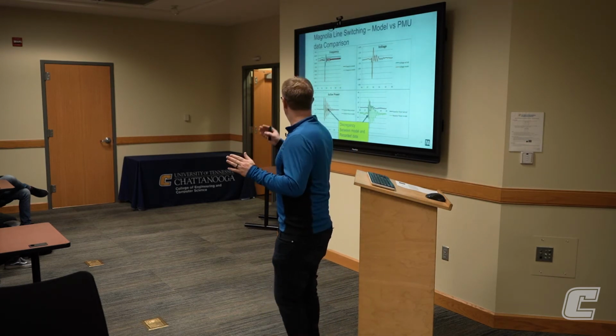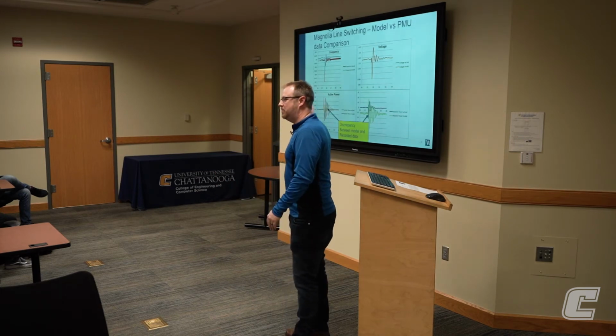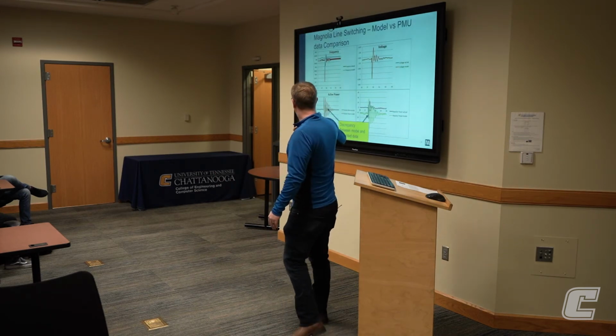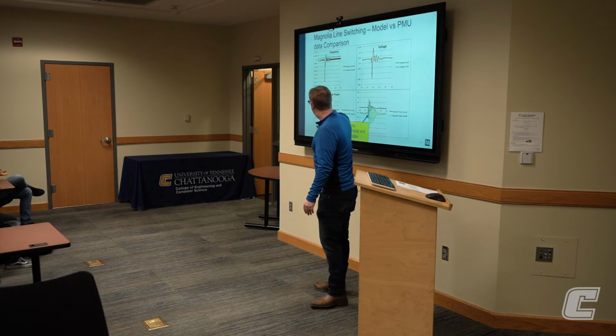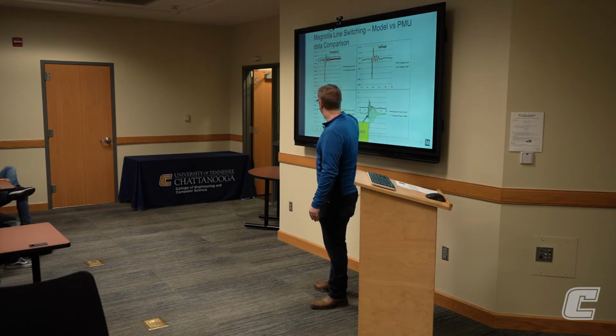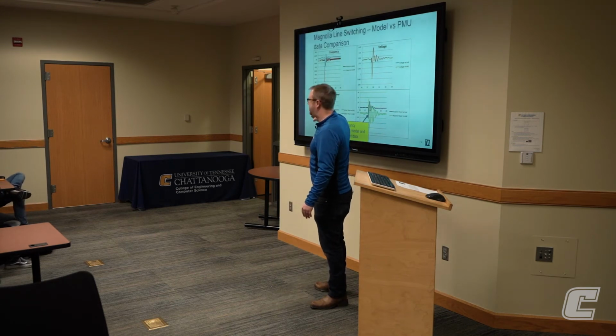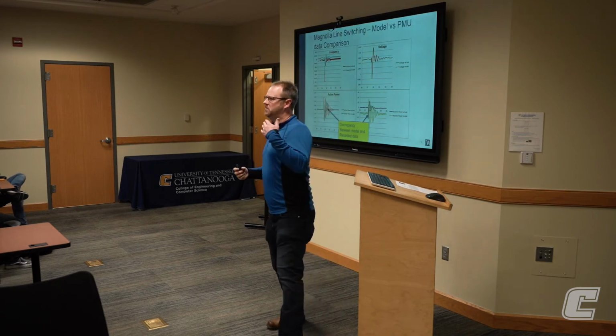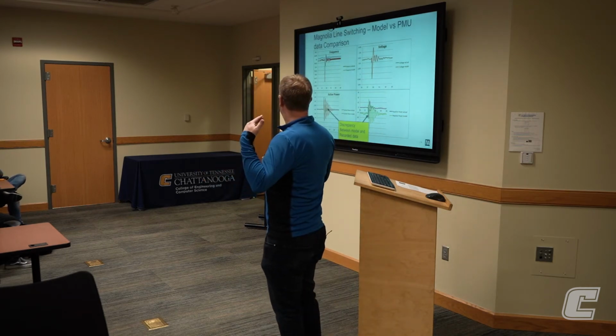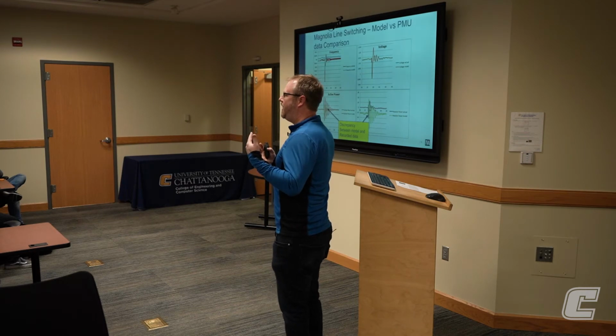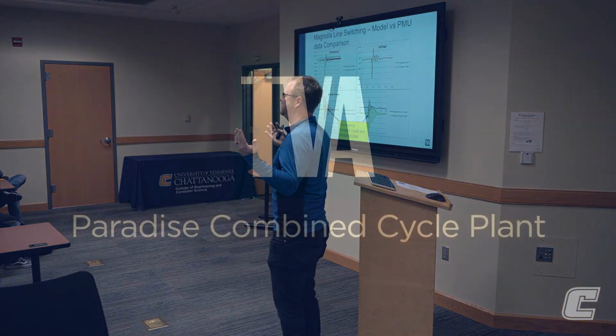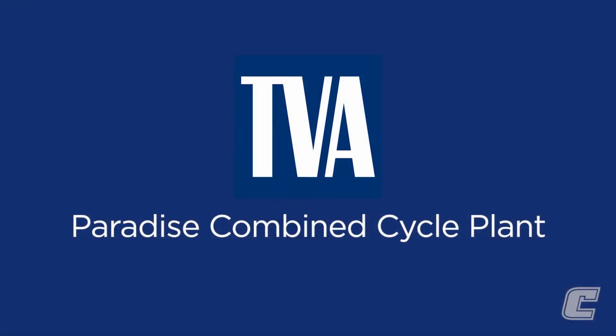So if you have devices like a PMU, you can record how your megawatts from your unit's output respond, and then compare how your units actually respond versus your model. Is your model accurate? Is your model responding how it does in reality when you have a fault on the system, or when something changes and you open or close a line?